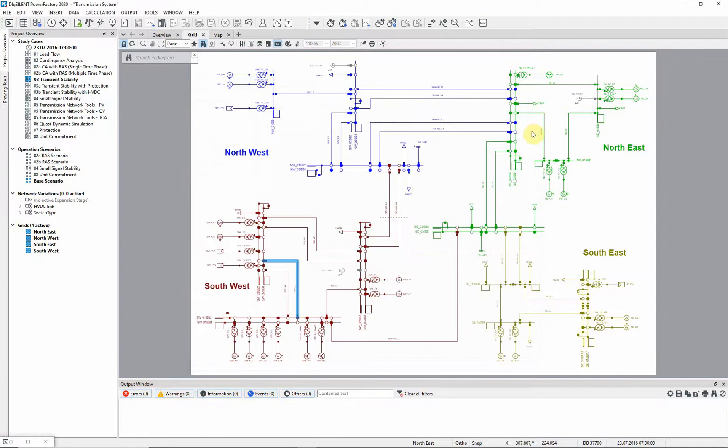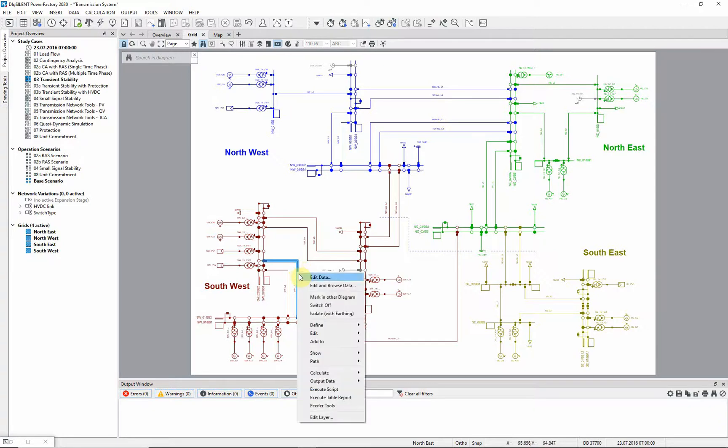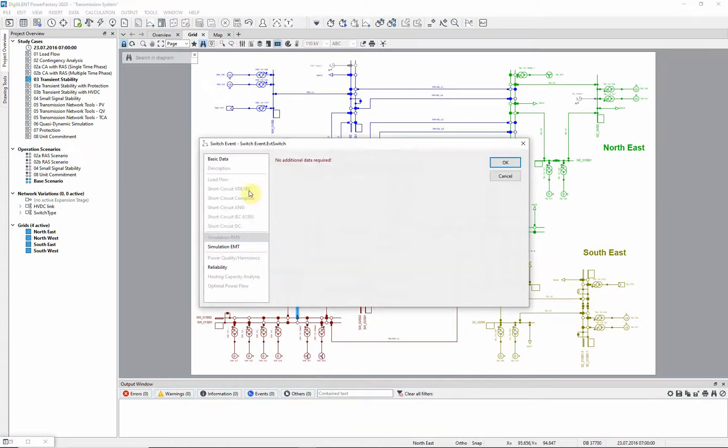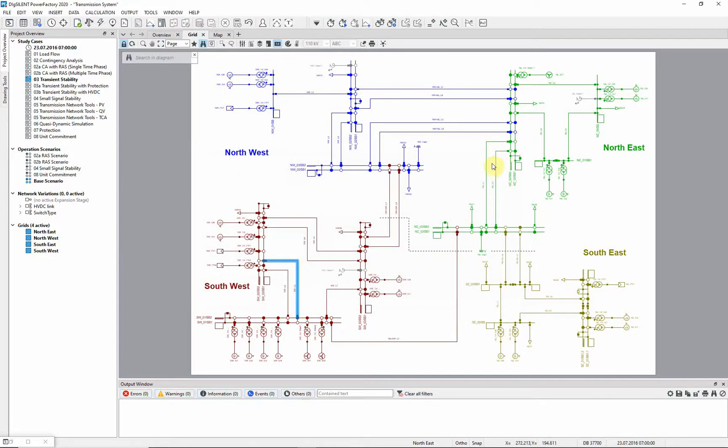We also need to clear the event after a suitable interval. Therefore, a second event is defined to open the circuit breakers at the ends of the line. Again, right click on the line, but this time define switch event. We will assume that the breakers will open after 100 milliseconds. The events are now set up.